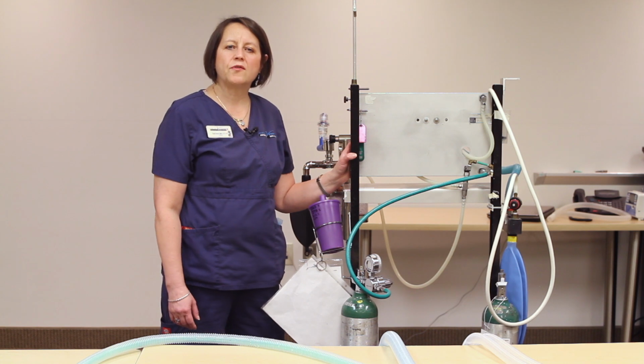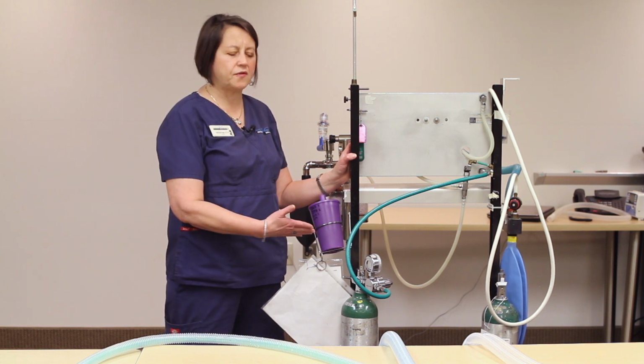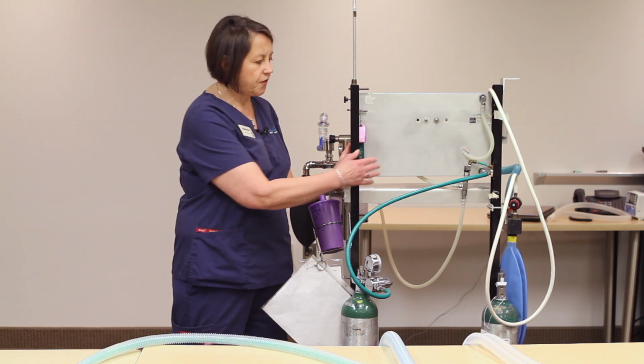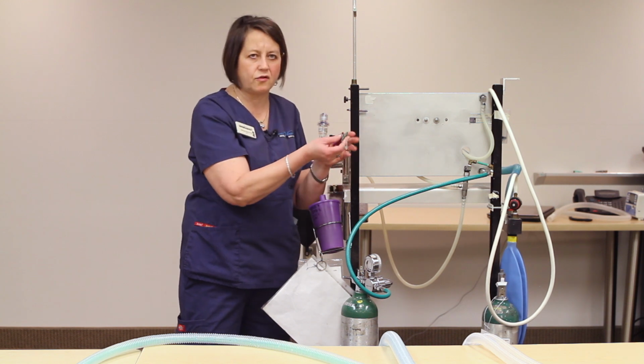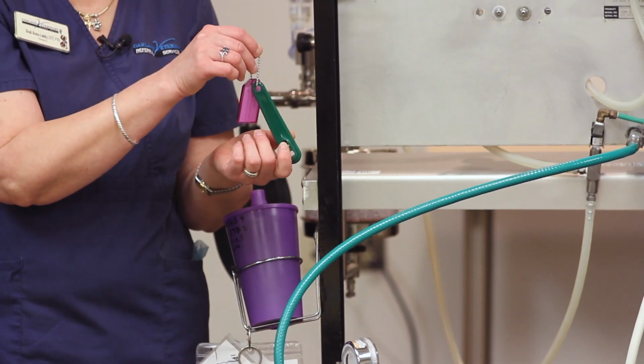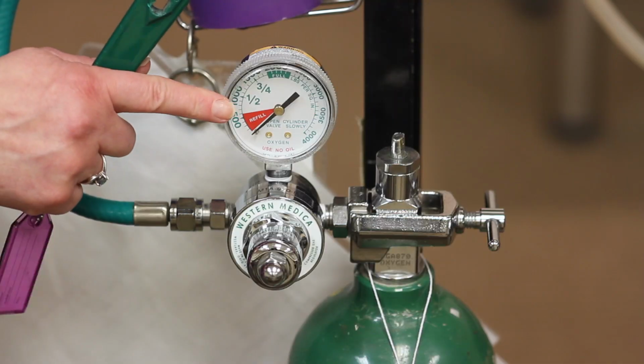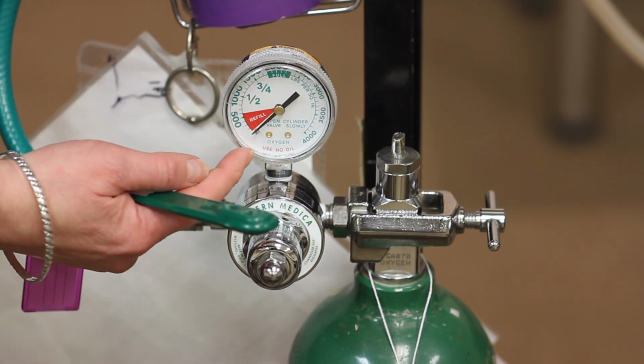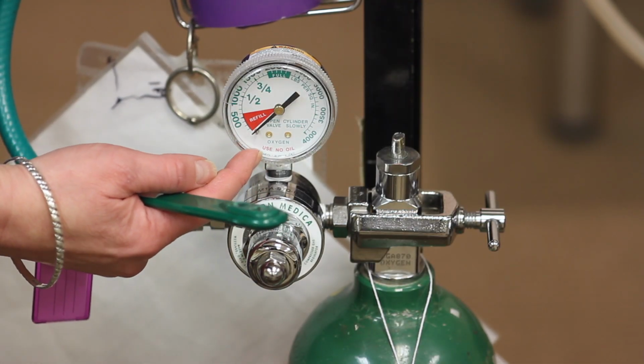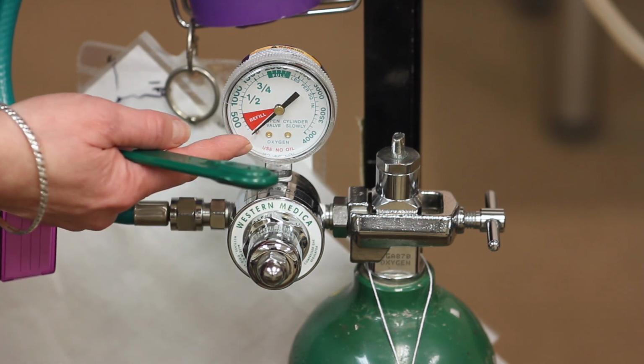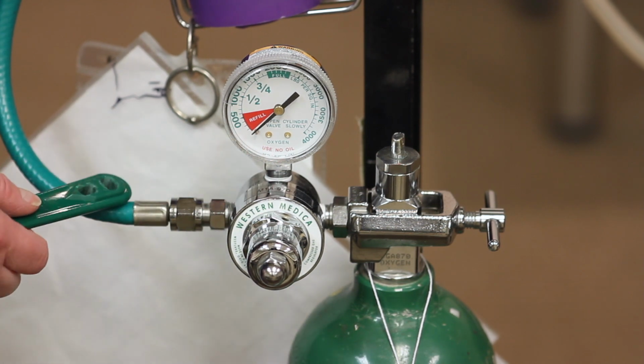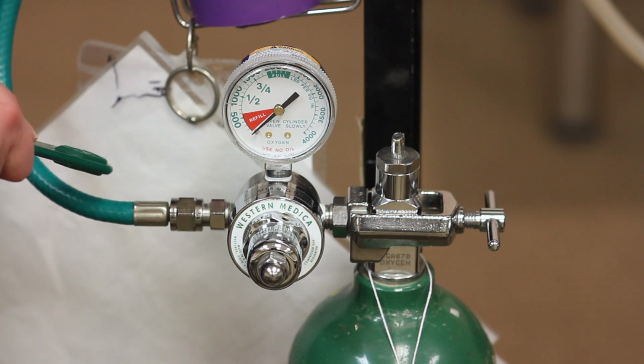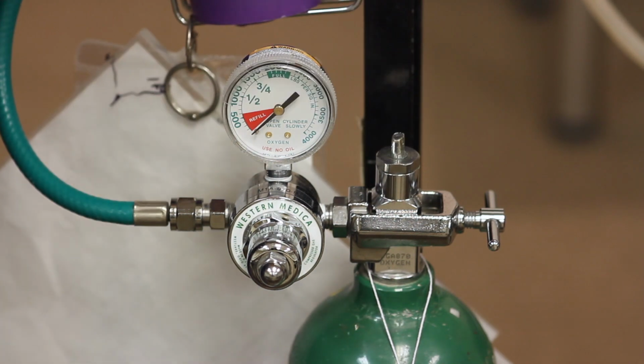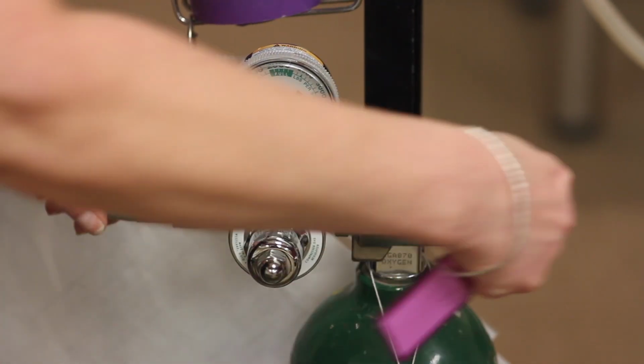So what we're going to do first is follow the flow of gas through this EVAD machine. The first thing you're going to do is turn on your oxygen supply, the wrench on the back of the machine. Right now the needle is down at the post, which means this tank is either empty or not turned on. We try to store these in the off position, so we'll go ahead and open that oxygen supply.